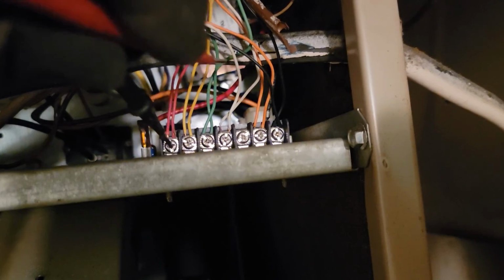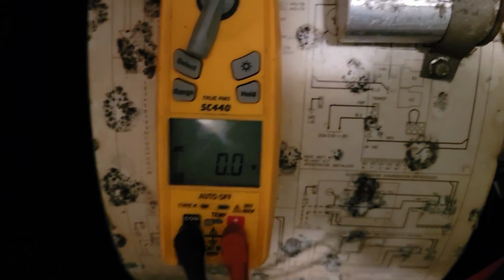Let's check from our R to C. See if we got 24 volts. No voltage. Okay, so now we need to check the transformer. Power coming in, power going out.